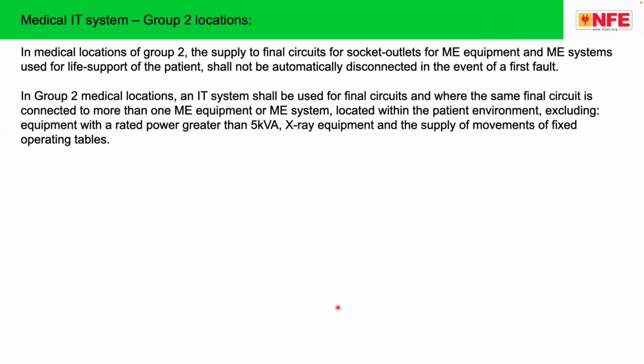Medical IT system. Medical IT system is a very special power supply system for Group 2 medical locations. Group 2 is a medical location where the life of the patient depends on the medical electrical equipment. Any disconnection of the power supply to the medical electrical equipment will be fatal to the patient. The patient may die. Sometimes multiple devices are connected to the patient, sometimes 3, 4, 5, 6 pieces of equipment are used in this particular area. Imagine you have 6 pieces of equipment connected to the patient's body or used somewhere nearby, and the seventh is a faulty equipment. As soon as you connect the faulty equipment, if the supply MCB trips, that's it. You will be in deep trouble.